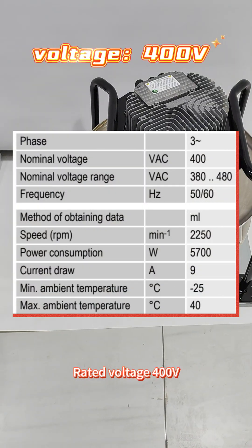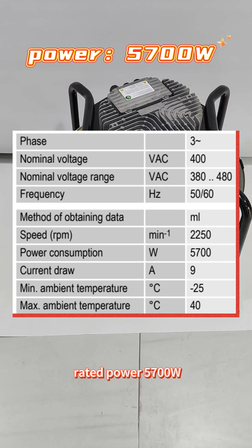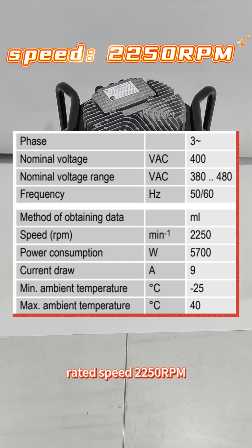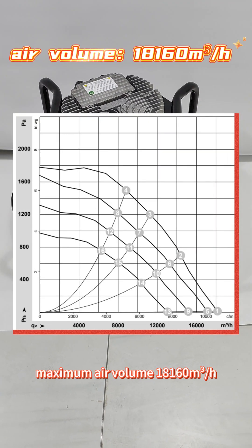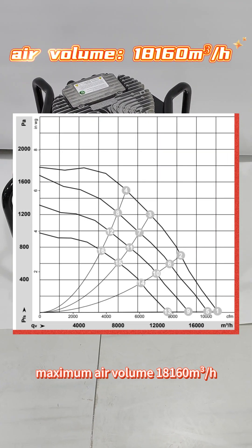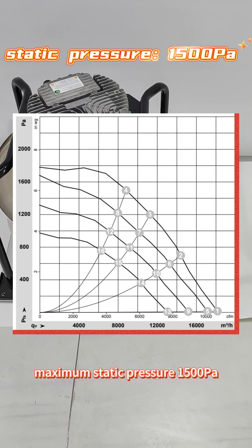Here are its parameters. Rated voltage 400V, rated current 9A, rated power 5700W, rated speed 2250RPM, maximum air volume 18160m³ per hour, maximum static pressure 1500Pa.